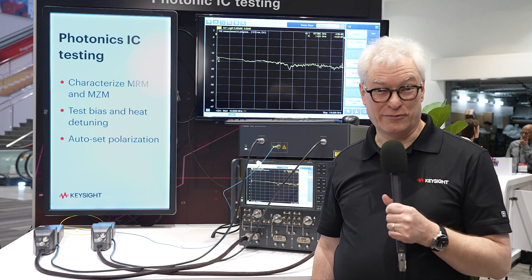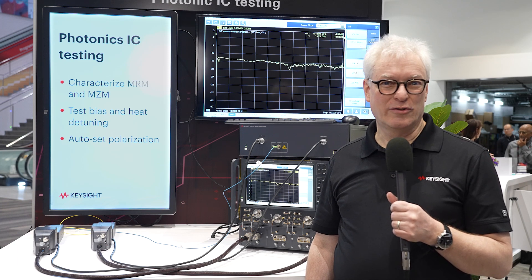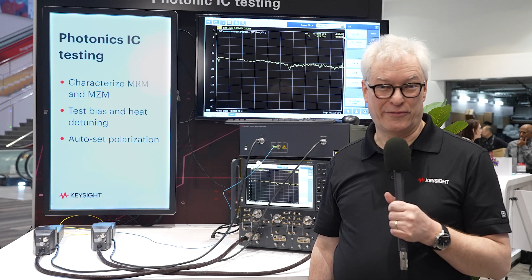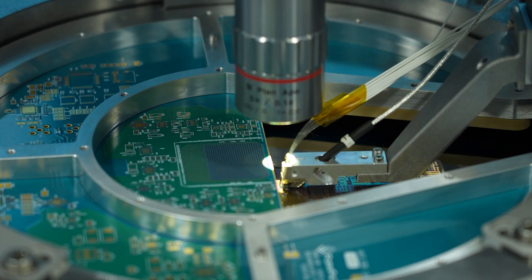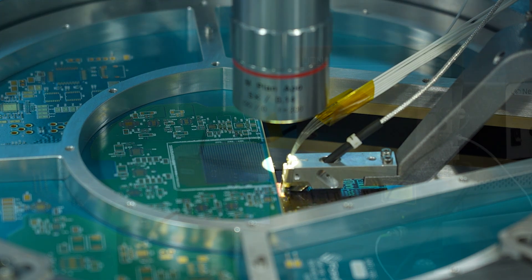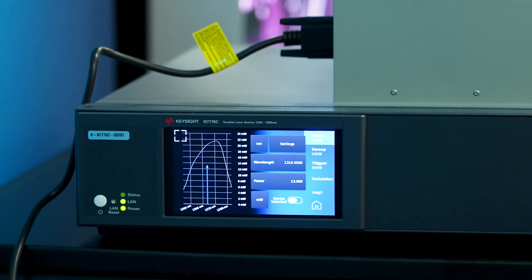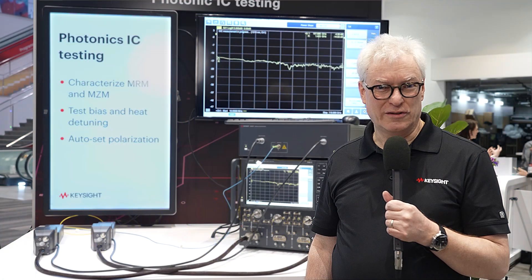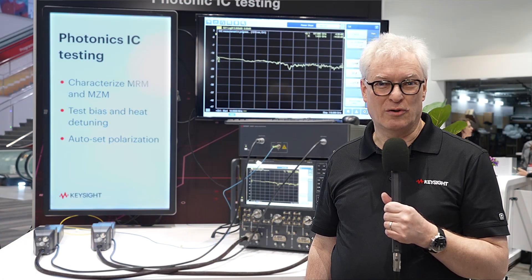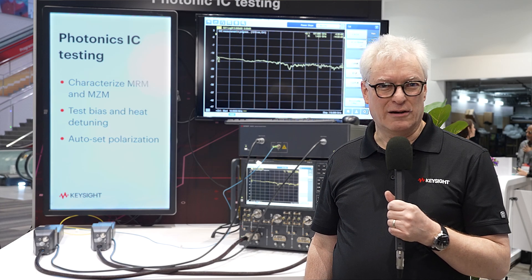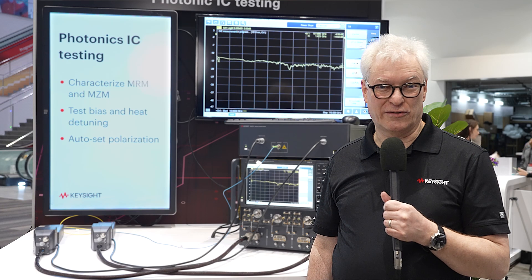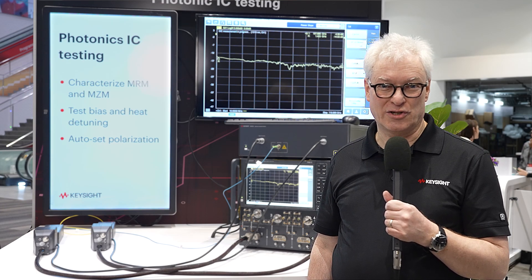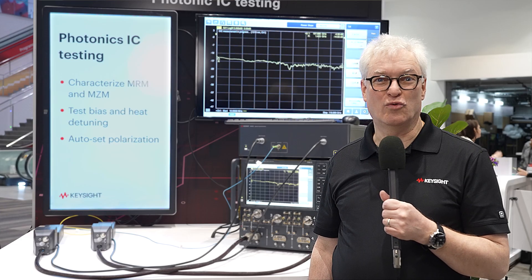Hello, I'm Stefan Löfler, product manager for photonics with Keysight Technologies. To introduce our PIC testing solution, let's visit our partner FormFactor at their booth. This CM300 wafer prober by FormFactor is equipped with the Keysight tunable laser, polarization synthesizer, and multiport power meter. The entire system is controlled by FormFactor's test executive using our PathWave test plugin and our polarization lambda scan software. This product family covers 1240 to 1650 nanometers, and with up to three lasers and an optical switch, the software combines their wavelength sweeps into one trace.